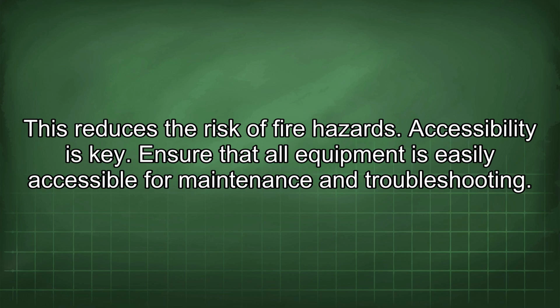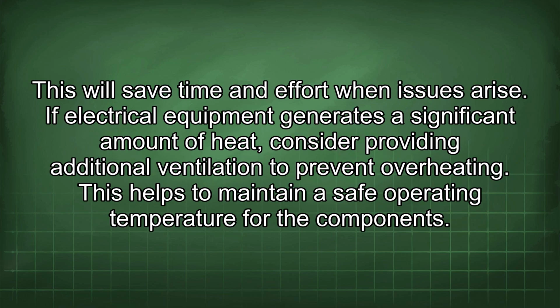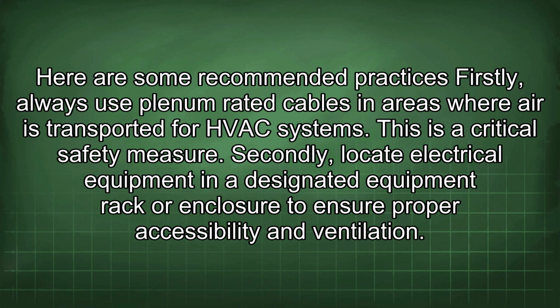Accessibility is key. Ensure that all equipment is easily accessible for maintenance and troubleshooting. This will save time and effort when issues arise. If electrical equipment generates a significant amount of heat, consider providing additional ventilation to prevent overheating. This helps to maintain a safe operating temperature for the components. Here are some recommended practices. Firstly, always use plenum-rated cables in areas where air is transported for HVAC systems. This is a critical safety measure.